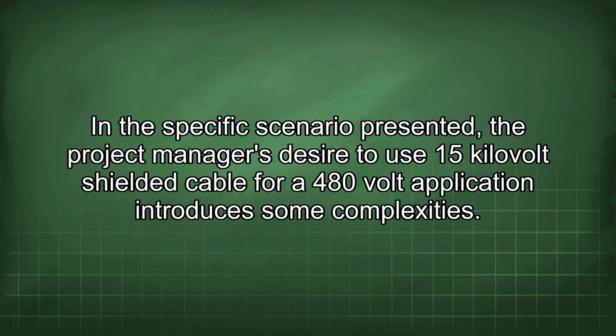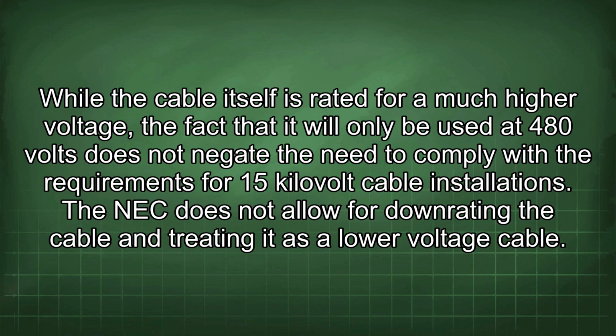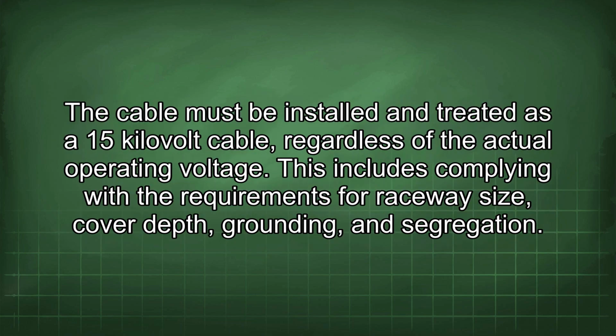In the specific scenario presented, the project manager's desire to use 15 kV shielded cable for a 480 volt application introduces some complexities. While the cable itself is rated for a much higher voltage, the fact that it will only be used at 480 volts does not negate the need to comply with the requirements for 15 kV cable installations. The NEC does not allow for downrating the cable and treating it as a lower voltage cable. The cable must be installed and treated as a 15 kV cable regardless of the actual operating voltage.